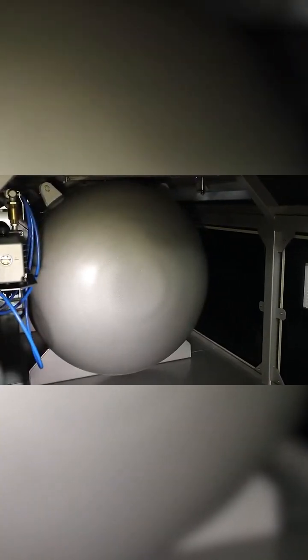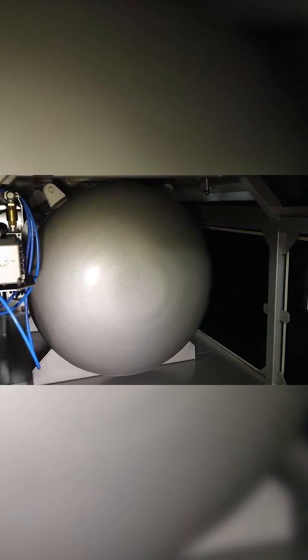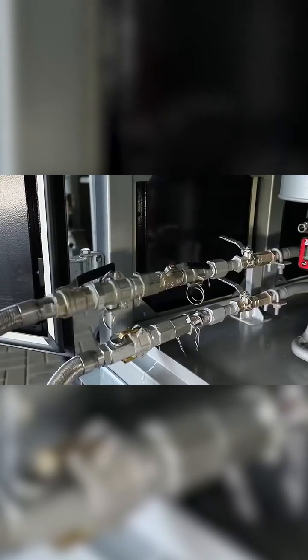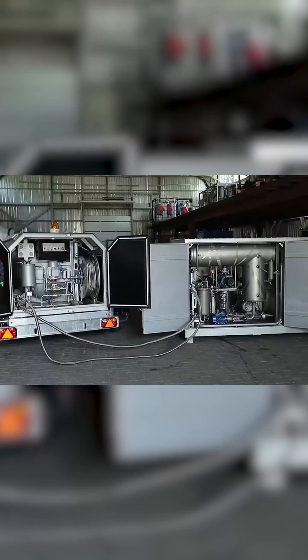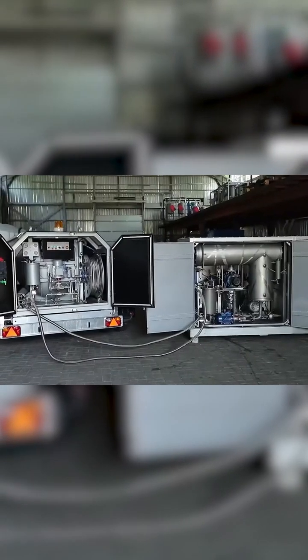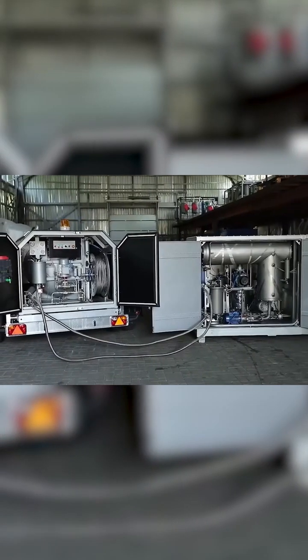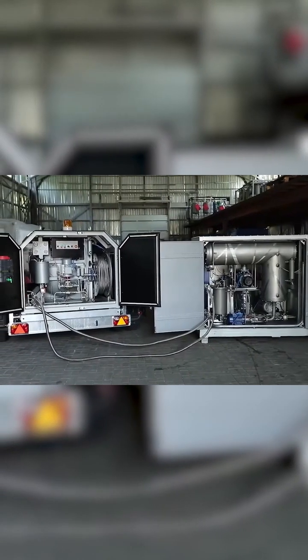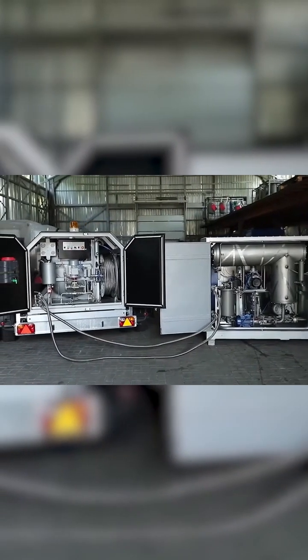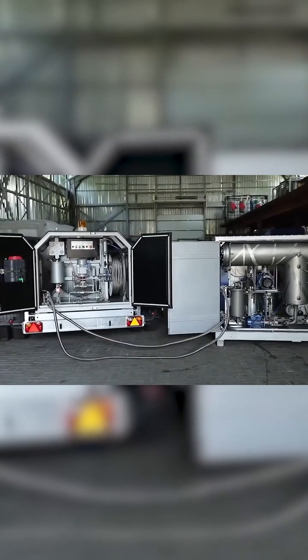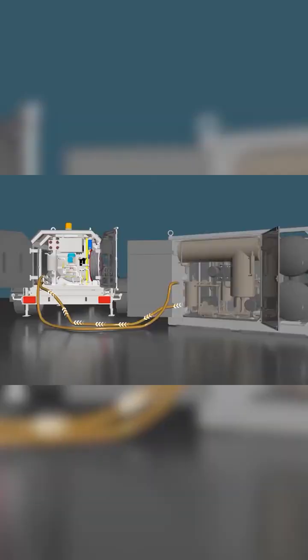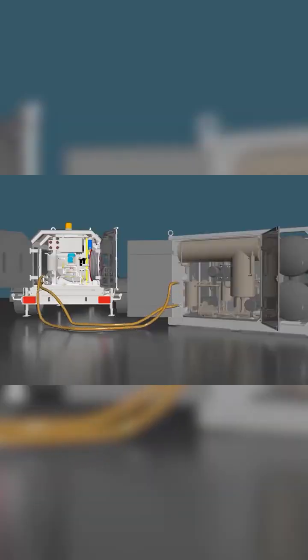This tank can also be used in the process of oil preparation. For this purpose, separate inlet and outlet lines are provided to connect a degassing unit to. In this case, the oil circulates in a closed loop through the tank and the degassing unit until its quality parameters reach the desired values.